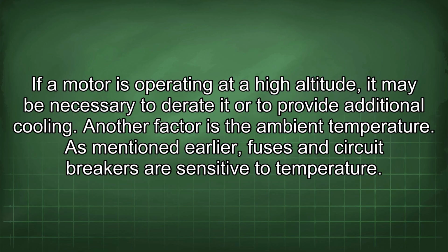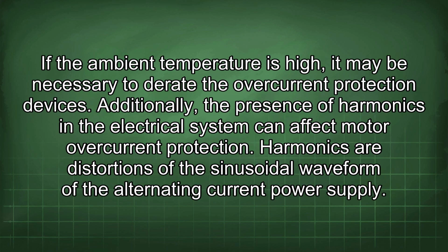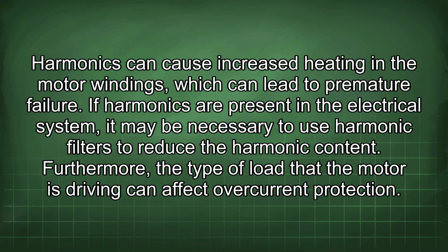As mentioned earlier, fuses and circuit breakers are sensitive to temperature. If the ambient temperature is high, it may be necessary to derate the overcurrent protection devices. Additionally, the presence of harmonics in the electrical system can affect motor overcurrent protection. Harmonics are distortions of the sinusoidal waveform of the alternating current power supply. Harmonics can cause increased heating in the motor windings, which can lead to premature failure. If harmonics are present in the electrical system, it may be necessary to use harmonic filters to reduce the harmonic content.